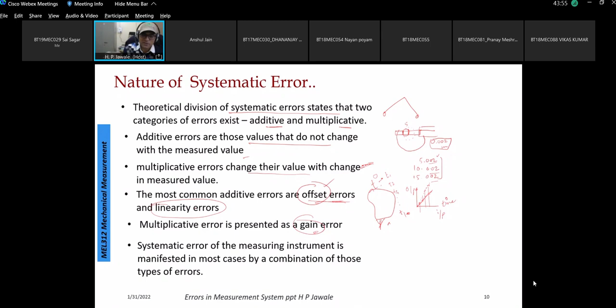The offset error is the difference, under specified conditions of use, between the actual output value and the specified minimum value of the output range, when the input is at the lower range value.